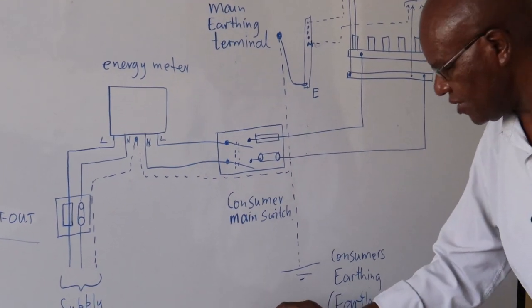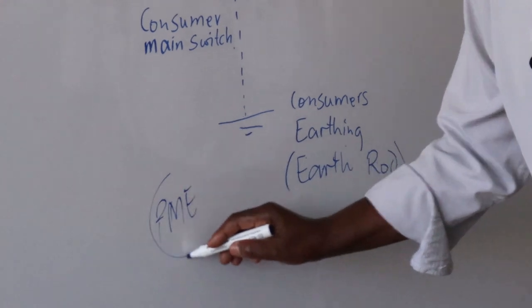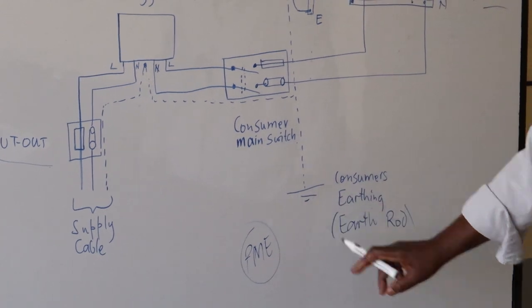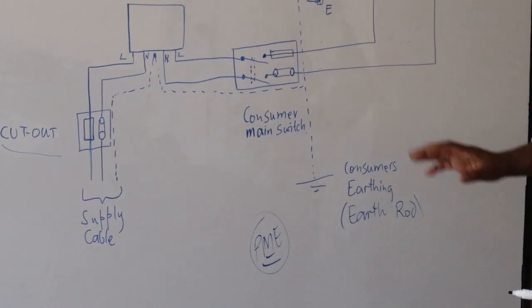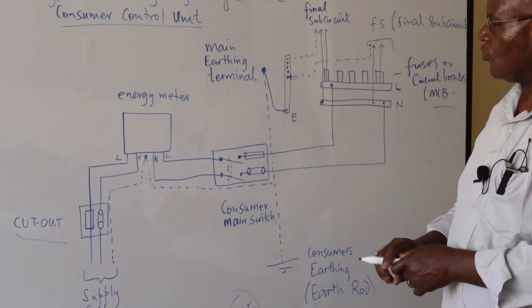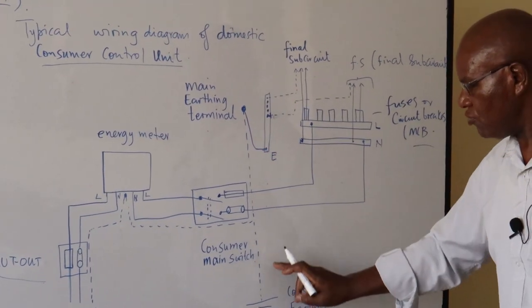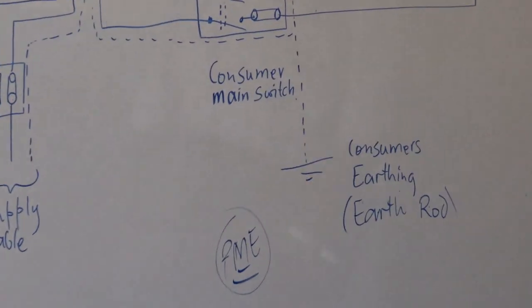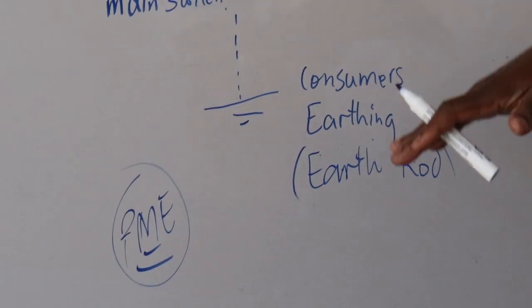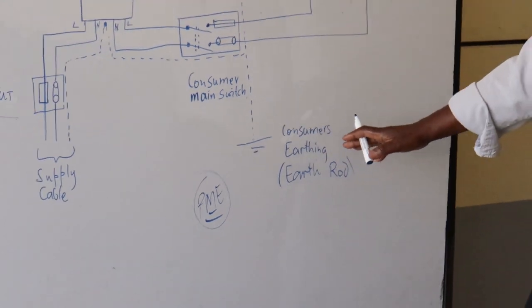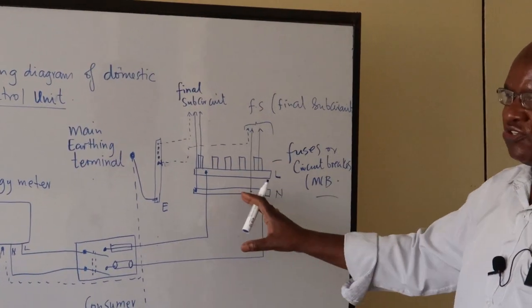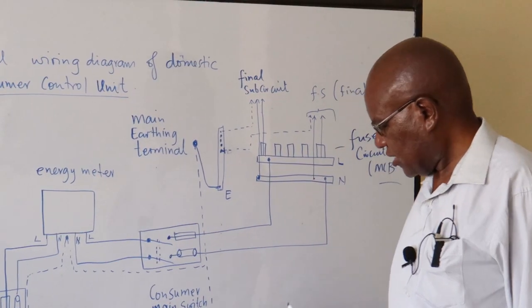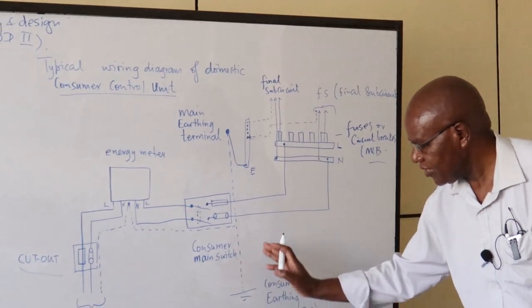In what we call the PME system, the power supply earthing terminal will be connected to the consumer's earthing terminal. Otherwise, in the consumer's installation, you must have what you call a main earthing terminal, and from there you connect a cable to an earthing rod which is hammered into the ground. The length and how deep it should go — you need to take some measurements. When you finish your installation, you need to do some testing, and the testing will determine the length of rodding required.